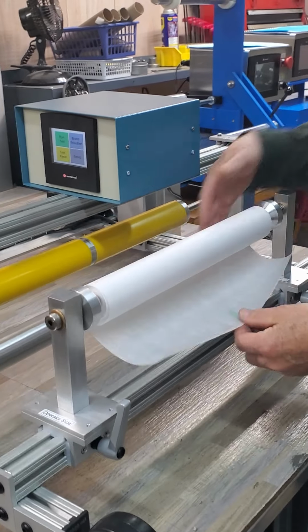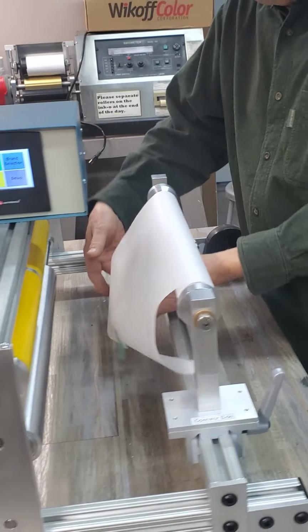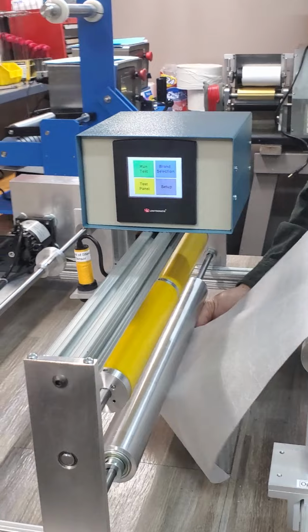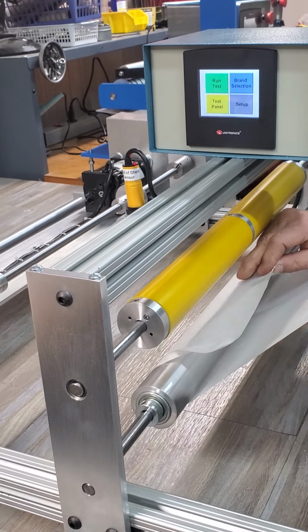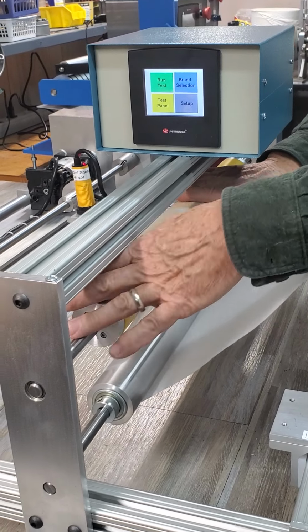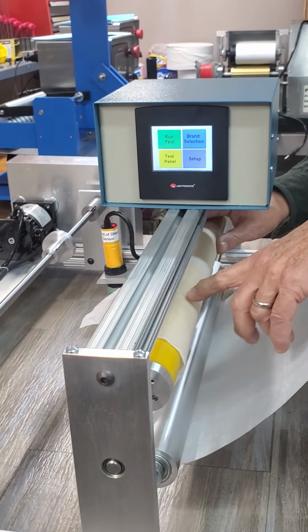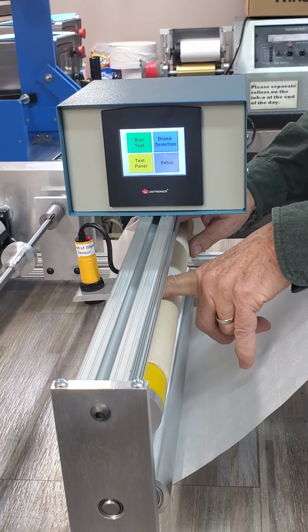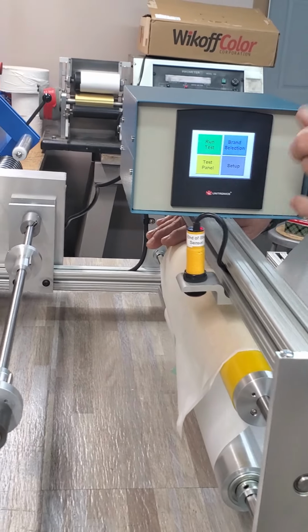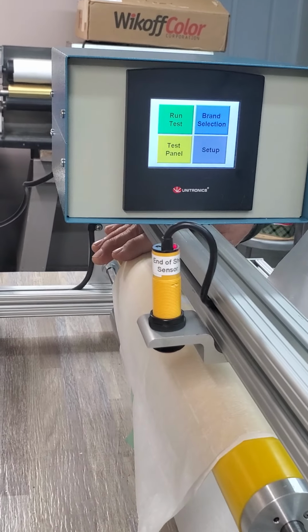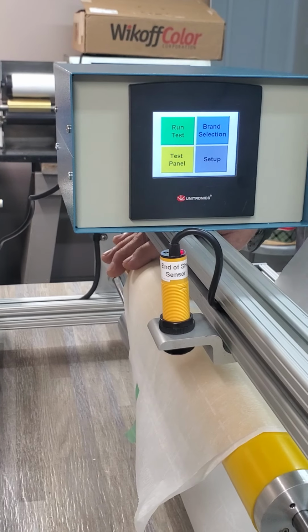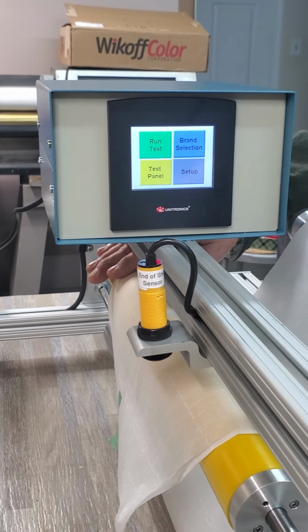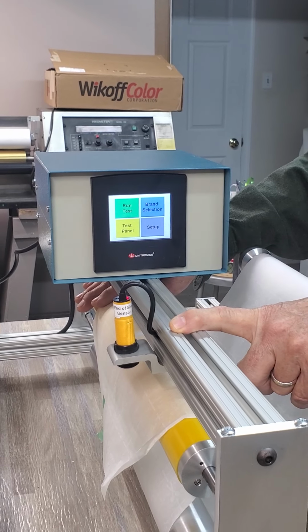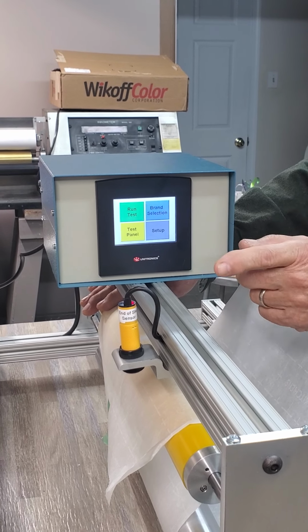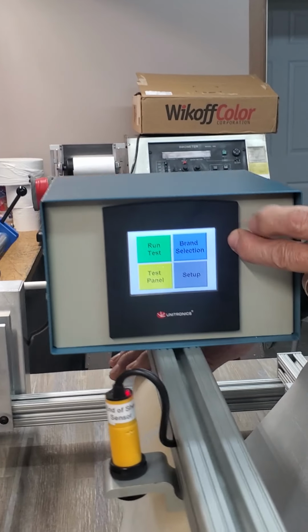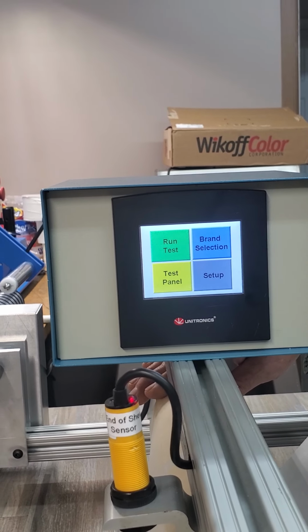Now the second part of this system is we have an S-wrap assembly. So what we're going to do is we're going to pass the sheet under the idling roll and over the sensing roll. This rubber sensing roll has an encoder at this end, and it's actually counting turns as we run the samples. You'll also notice up here we have what we call an end of sheet sensor, and essentially that's going to look for the trailing edge. When it passes under that, that tells the system that the roll has expired. It will shut off the test and display the final reading on the PLC. We're going to run a sample in a moment and demonstrate that.